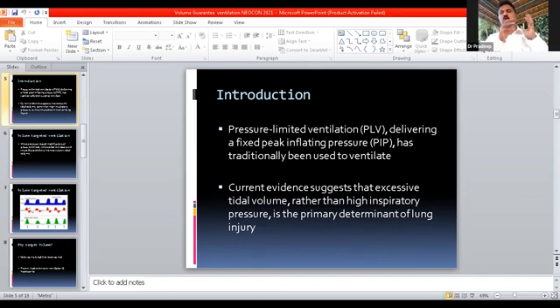beautiful job. You just pick up some ventilator which a company person comes and says, sir, my ventilator gives volume targeted. What it does is, after it reaches adequate volume, it switches off the pressures, which is not right. It just measures the inspired tidal volume, which is not the right thing to do. So what is important is to understand and know your machines very well before you start using them. But I'm sure if you have the right machine, right training and technique, you will do a good job with volume guarantee and you will do a very good job for your babies too.